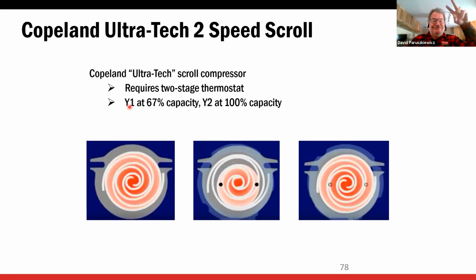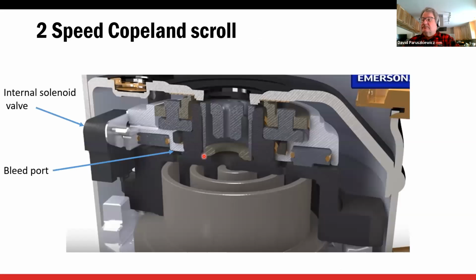So that on the low stage, we're only pumping 67%. So if we have, like, say, a 10-ton compressor, I'm only pumping about 7 tons, a little bit less than 7 tons, 67%, because we're bypassing some of the gas going through the compressor. And we do that with these 2 little bleed holes. So you can see the little bleed ports here. So what happens is when those bleed ports are open, we're bypassing some of the gas from suction discharge. We energize this solenoid, and it closes these ports. So on your high stage, we're going to energize this solenoid. This is internal in the compressor, so if that solenoid fails, we cannot replace it.